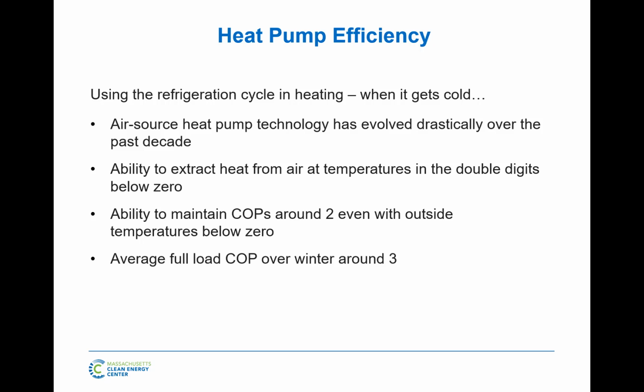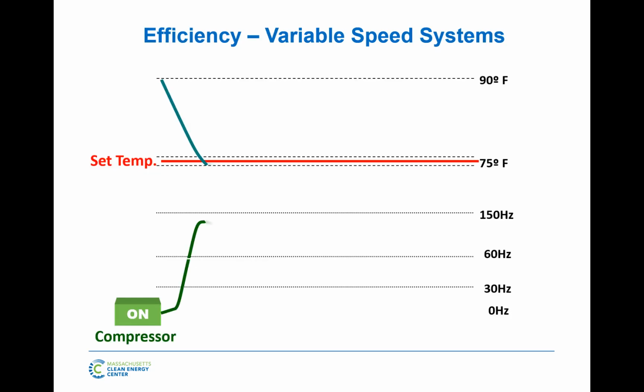So yes, at that point in time, on that day, at 0 degrees, on January 31st at 3 a.m. I'm making these dates up as a typical coldest day of the year. On January 31st at 2 a.m., when it's 0 degrees outside, your COP is going to be at around 2. At that point in time, if you had a high efficiency furnace, you'd be better off using that. But how many hours a year does that happen? And the rest of the year, you win with the air source heat pump. So unless you want to install both, which you can, and control between both, the air source heat pump usually still wins.